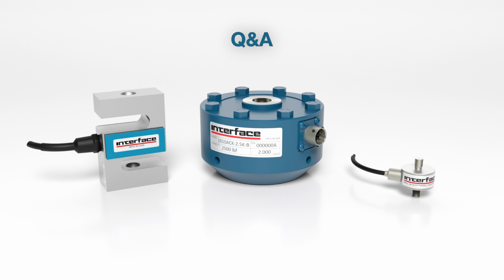They're coming in fast now, guys. Is there a rule of thumb for how much zero balance error is acceptable? Our nominal spec, I believe, is plus or minus 10%... once you see a drift, so it's 1%, I'm sorry. So 1% would be our nominal spec.